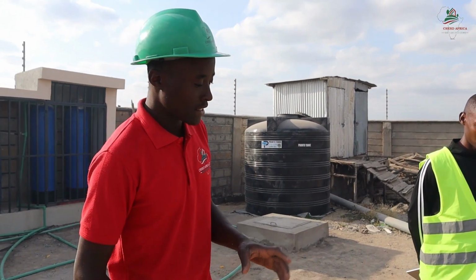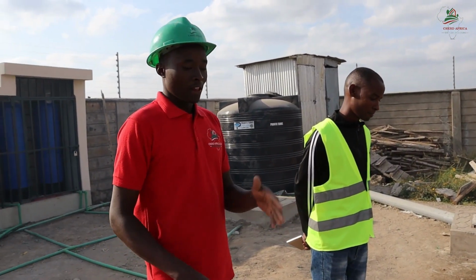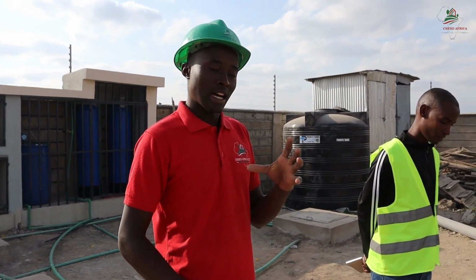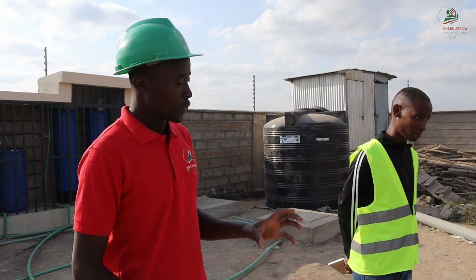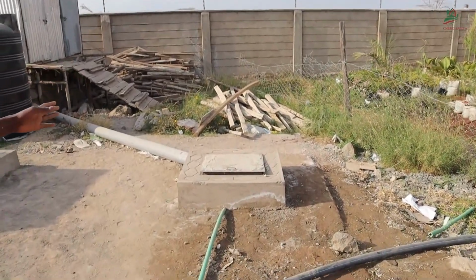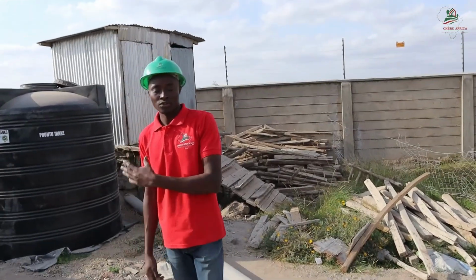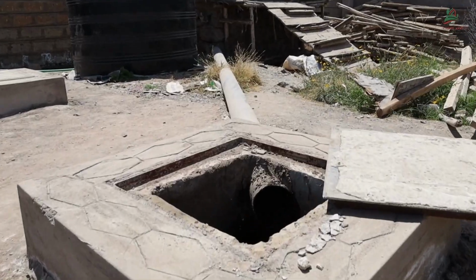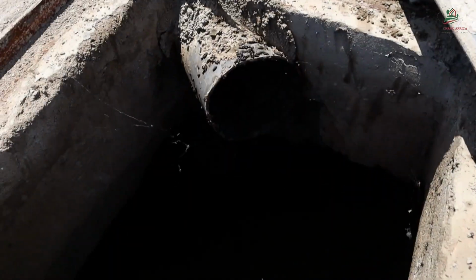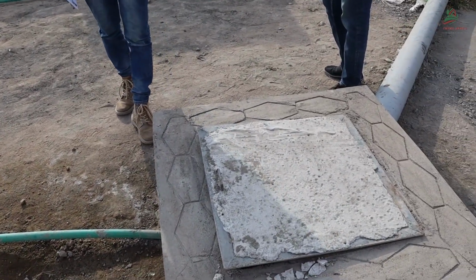What does that mean? It means that in this chamber, which is one, these two are just inspection manholes, but the chamber is one. The purpose is that large solids will be broken down into water, and at the exit, at this manhole here, the water coming from this side will be free of solids. So we need anaerobic bacteria, which means we don't need any oxygen in this chamber. If you open and check, you won't find any oxygen provisions in this chamber, so that we can have the essential breakdown of those solids by the anaerobic bacteria.